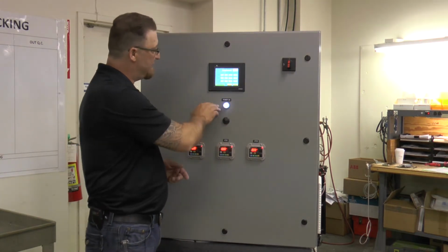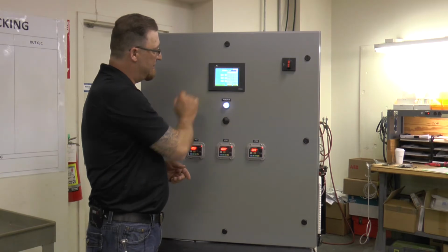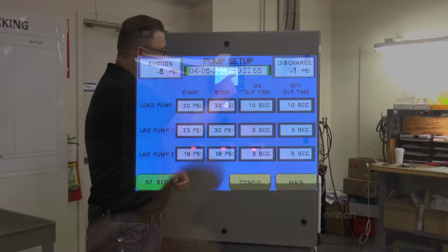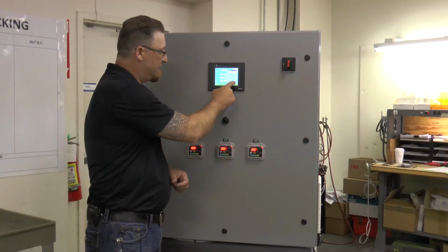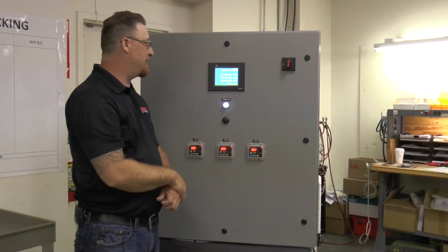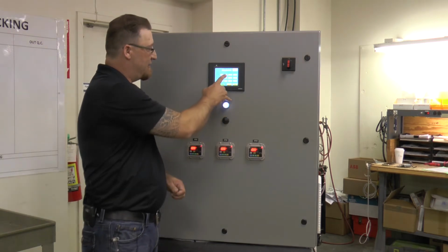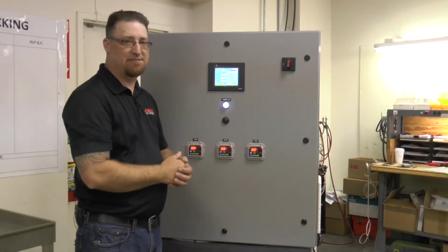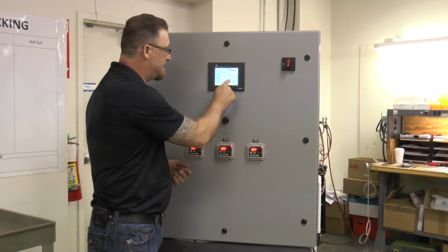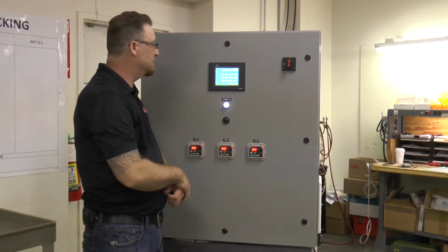So if I want to change the lead pump start pressure, I can simply press that button, and then I can change it to anything that you want. So my lead pump is starting at 25 psi, and I want it to stop, let's just say, for instance, 30 psi. So I can change that to 30 and press enter.